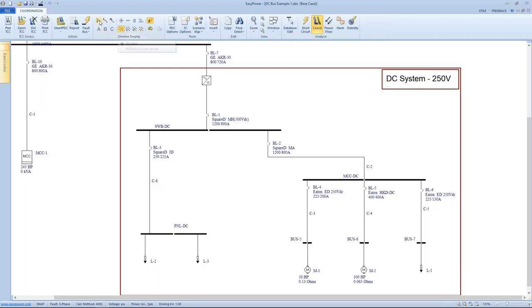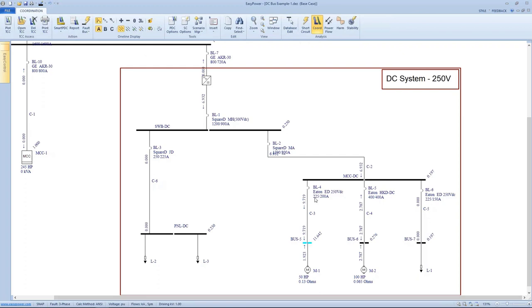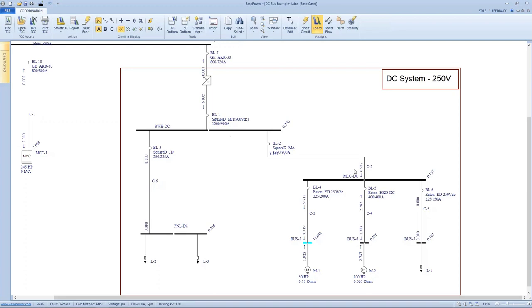If we look at the current levels in our coordination module, and we fault let's say a remote bus, it'll give us the current for that branch, and then the contribution currents from the remote buses and the remote sources of current. So if we have a fault on this particular bus, we're going to see some AC contribution, or at least some contribution from the rectifier during the first half cycle, and some feedback from the sister loads or the motors that are included on the bus.